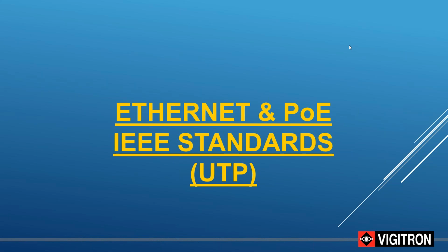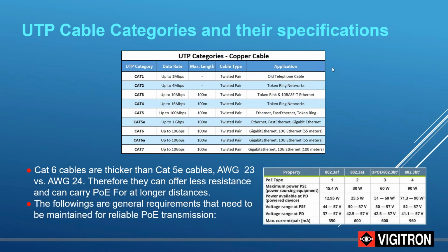The second applies to UTP or Ethernet cable installations, where IP-PoE installations require distances over the standard limit of 328 feet, 100 meters. So let's take a look at what the Ethernet and PoE standards for UTP say with regard to distance.